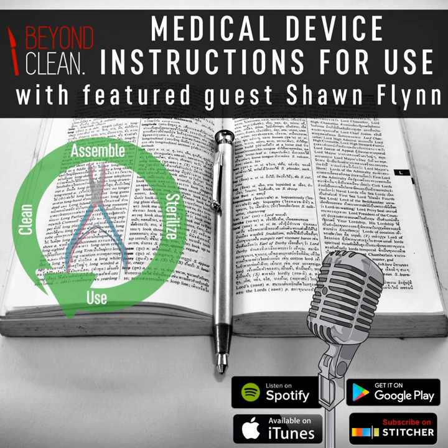That's a great question. I was recently consulting for a hospital in Florida, and I got a call about cycle times and pulse rates. This was a gravity cycle that the manufacturer was recommending, but all the sterilizers in that hospital are set for pre-vac. So unless you have somebody in sterile processing who understands how to change those cycles on the sterilizer, one of two things happens: either they don't process that device, so they don't purchase it, or they improperly sterilize it on the wrong cycle, which gets them in trouble if that's ever caught on an inspection or internal audit.